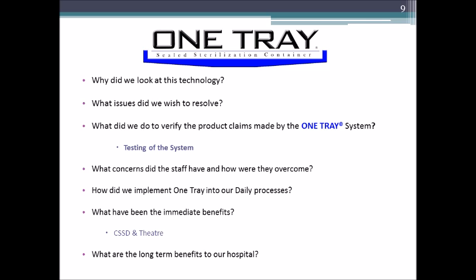That's a significant amount of not only electricity and time savings for the department, but if you're familiar with the way that a sterilizer works, during the dry time, typically the autoclave is pulling a vacuum, and holding those instruments in a vacuum state for a set period of time. The way that the autoclaves typically pull that vacuum is through a Venturi system, through running water over a Venturi valve, which creates that vacuum.